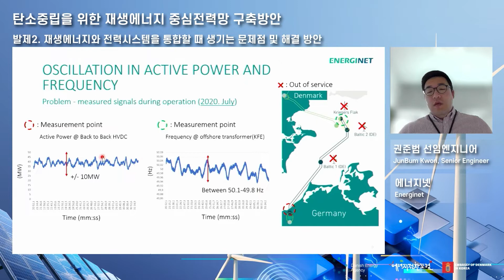Between active power and non-active power, there was an erroneous control tuning that led to plus or minus 200 megawatts fluctuation. The HVDC converter station, Baltic Wind Farm, and Kriegers Flak created some oscillation.